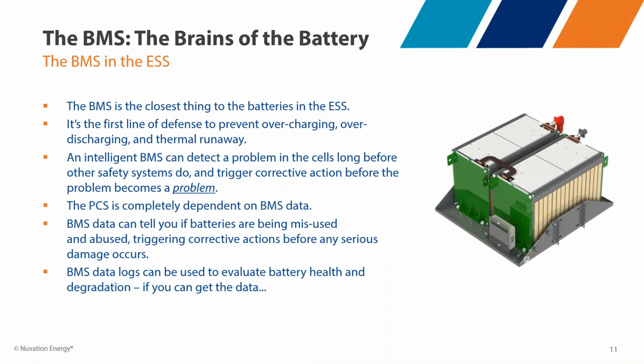The BMS is really the thing that's closest to the batteries in the energy storage system. It's the first line of defense to prevent things like overcharging, over discharging, and detecting thermal runaway, taking a system offline. The differentiation is that an intelligent BMS can actually detect that problem long before other safety systems do, and trigger corrective action before it becomes a bigger problem.